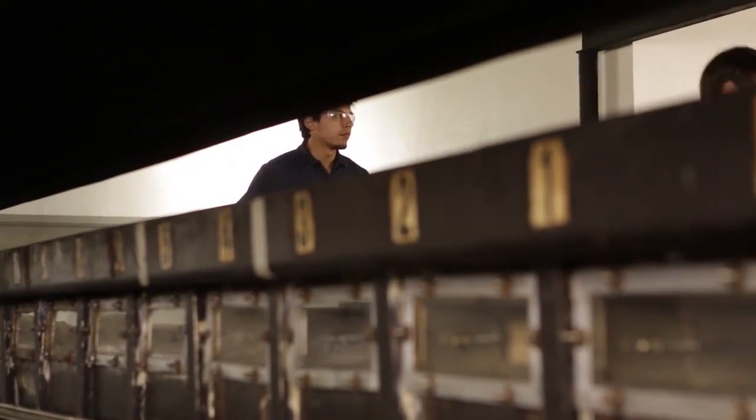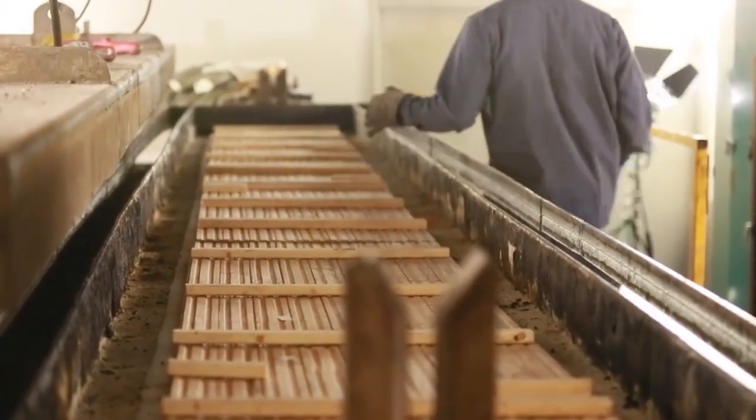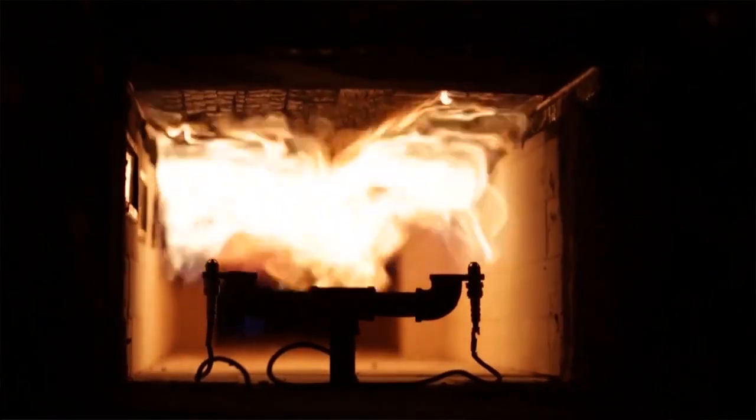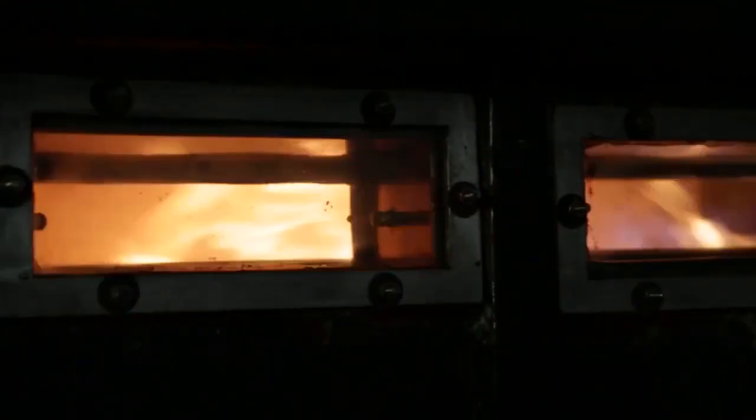This test specimen is horizontal and it extends 24 feet, the entire length of the tunnel. The igniting flame is located at one end, and the igniting flame itself is 4.5 feet in length. So that's the exposing flame. And then essentially we measure the distance that the flame travels as well as the rate at which the flame travels beyond 4.5 feet. And we use that information, that data, to develop the flame spread and smoke developed ratings.